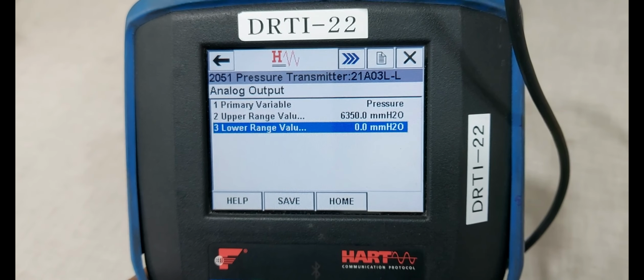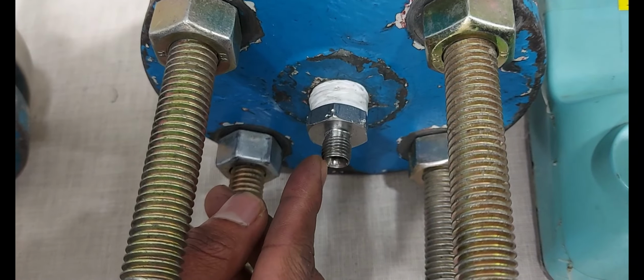First we are removing the low side tube. Okay, low side tube we have removed. Next we are removing the high side tube also. We are connecting the tube, pressure calibrated tube connected to the high side only. Low side tube already removed. Low side port is open to atmosphere now.